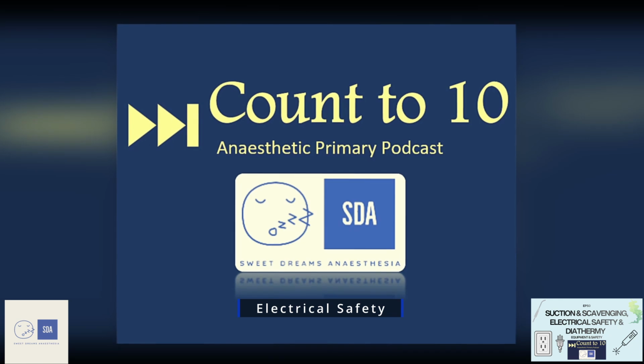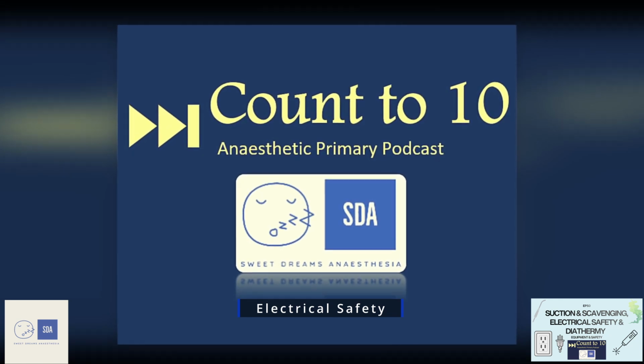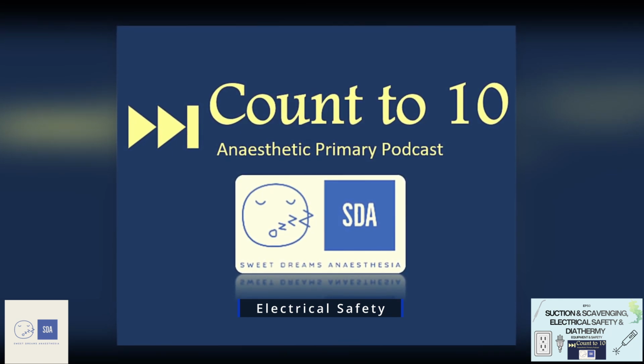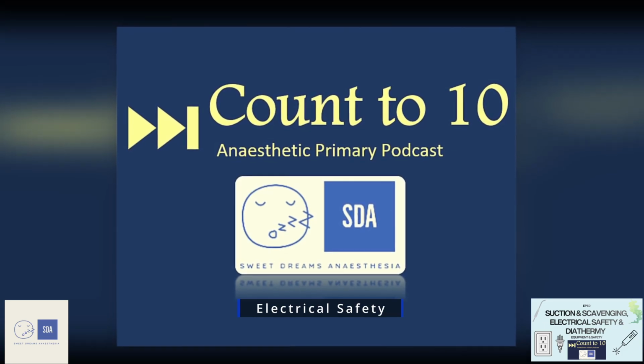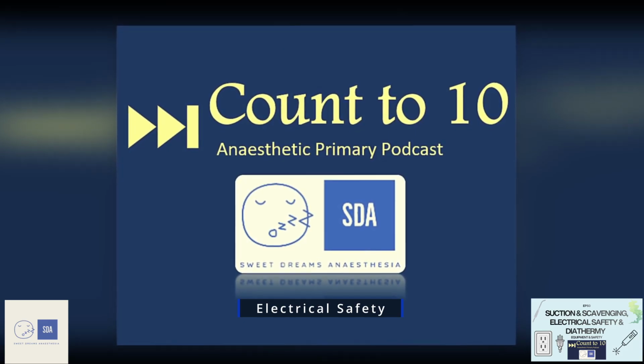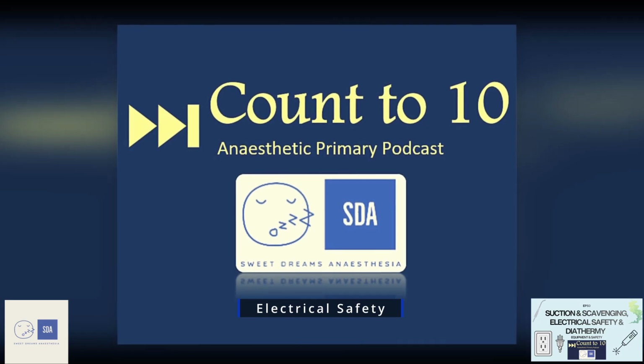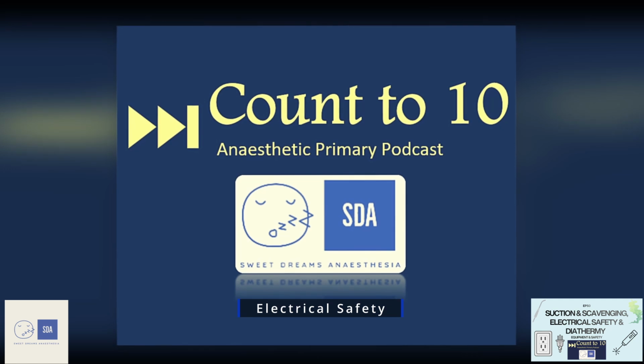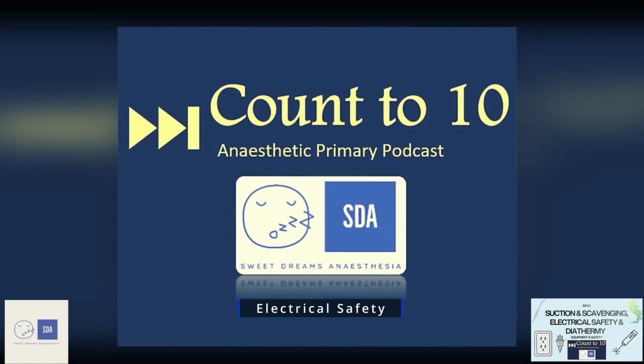In the same way the packaging has to display what that level of safety is for each type of applied part to that patient, so does each area within a hospital. And for specific areas in the hospital, specifically the operating theatre or critical care areas, they have to be at a level of protection which we call cardiac protected treatment areas. And the way you tell that again is through the symbol of a heart in a box. So because they need to be at that high level, what they then need to have is that EES system as our safety system within each operating theatre room.